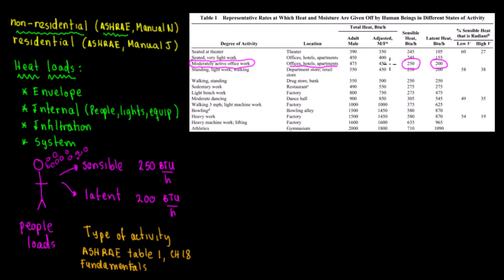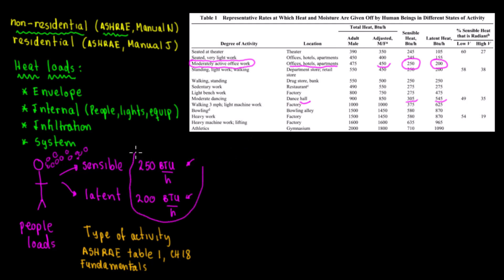In residential design, for a one-bedroom apartment we typically put one person and use 250 and 200 BTU/hr. However, if you're in a gym or a dancing hall, the values change — for a dancing hall, sensible is 305 and latent is 545 BTU/hr. This is because it depends on the metabolic rate and type of activity.